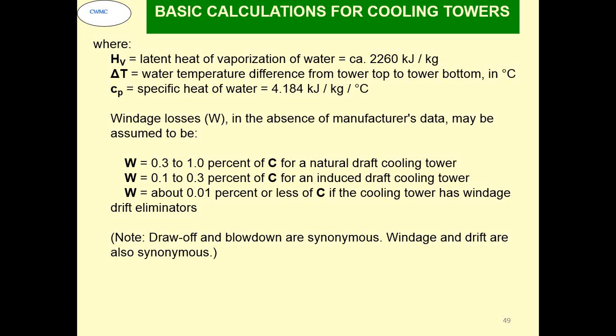Windage losses W, in the absence of manufacturer's data, may be assumed to be 0.3 to 1% of C for natural draft, 0.1 to 0.3% of C for induced draft cooling towers, and about 0.01% or less with drift eliminators. But as I said, if you have good drift eliminators, you can go to 0.005.